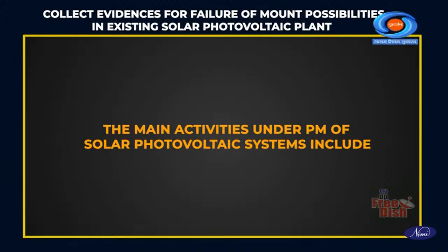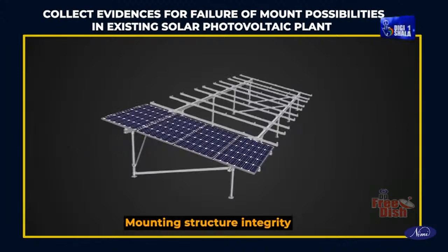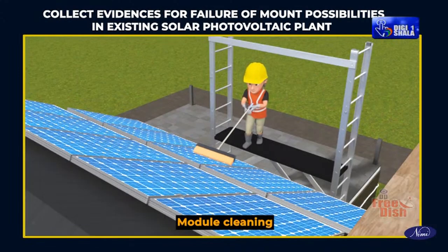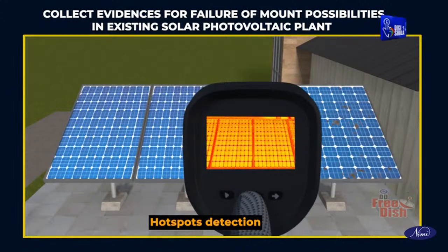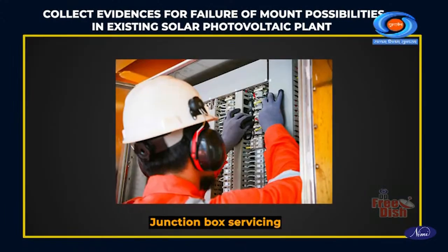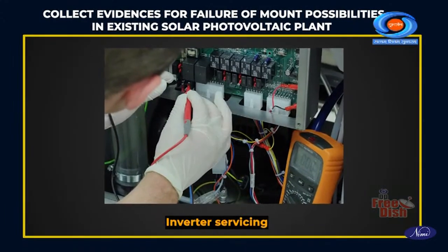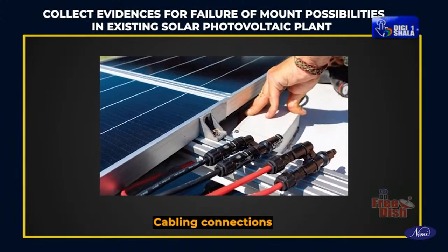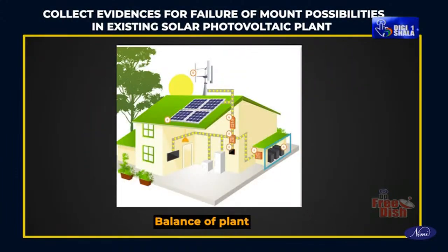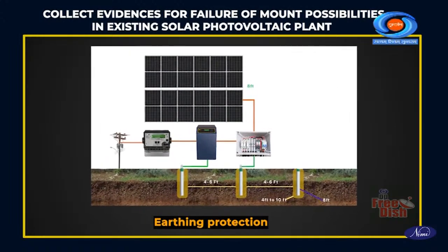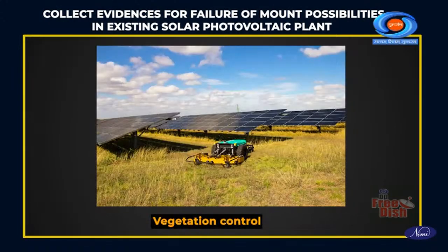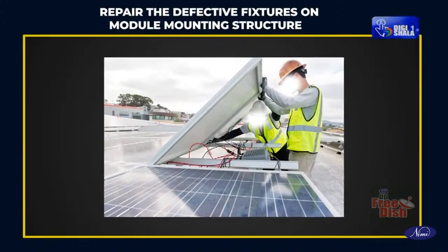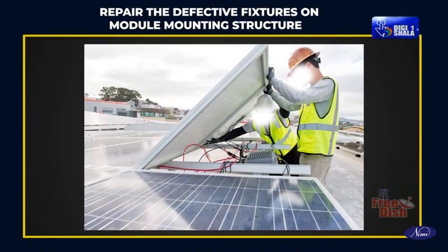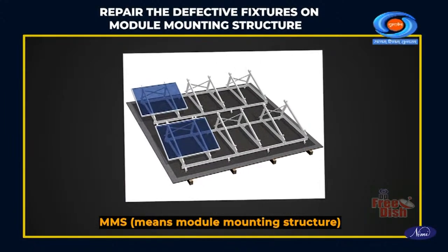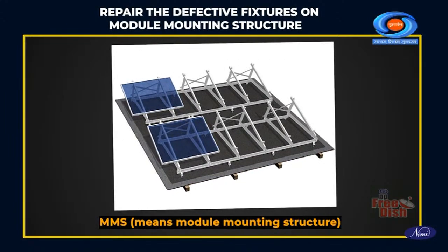The main activities under PM of a solar photovoltaic system include mounting structure integrity, module cleaning, hot spots detection, junction box servicing, inverter servicing, cabling connections, balance of plant, earthing protection, vegetation control. Repair the defective fixtures on the module mounting structure. MMS means module mounting structure.